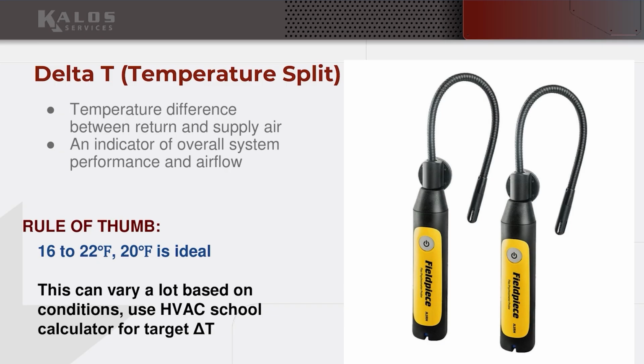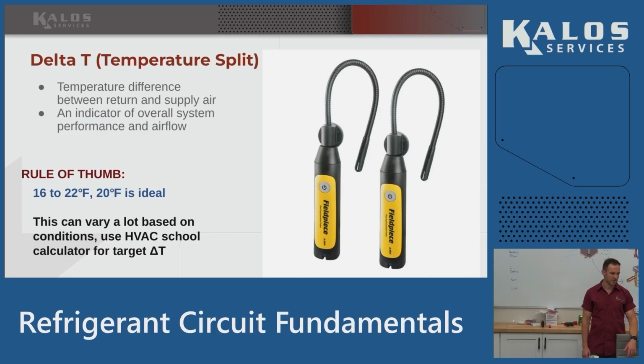Return and supply, yep, and those psychrometers will measure the humidity and the dry bulb temperature as well. So they can give you all the numbers you need, and you just have to figure out whatever the outdoor temperature is. I usually just look at the weather, but that'll get you close enough. Yeah, that's been working for me. I've seen that, it's usually pretty good.